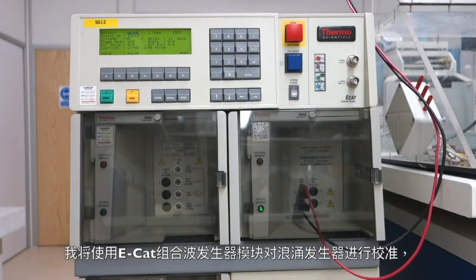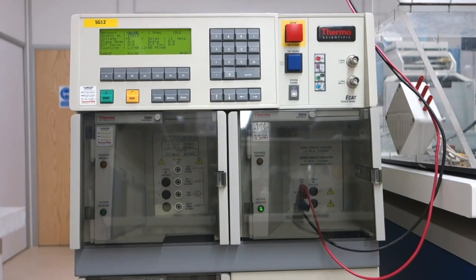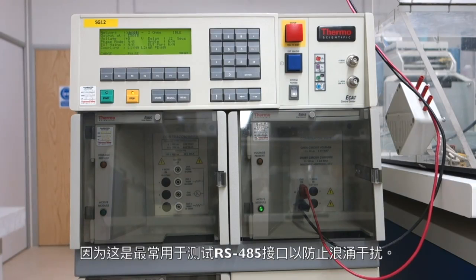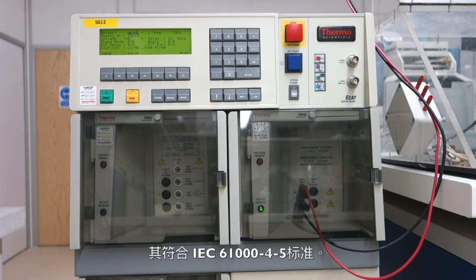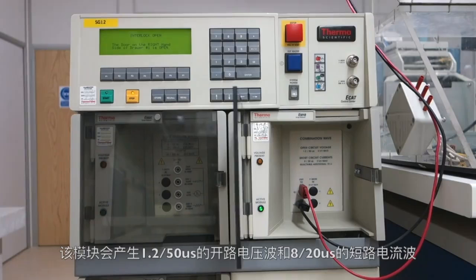I'm going to do the calibration of the surge generator using the ECAT combination wave surge generator module, because this is the most commonly used for testing RS-485 interfaces against surge. It's called up by the IEC 61000-4-5 standard, for instance. This module will generate a voltage waveform of 1.2 microseconds rise time and 50 microseconds fall time to the half amplitude mark when open circuit, but an 8 microseconds rise time, 20 microseconds fall time current into a dead short.